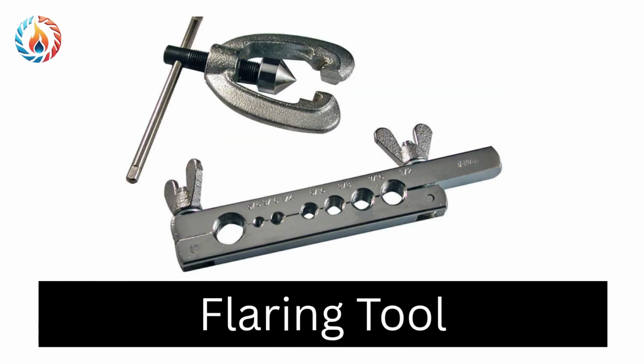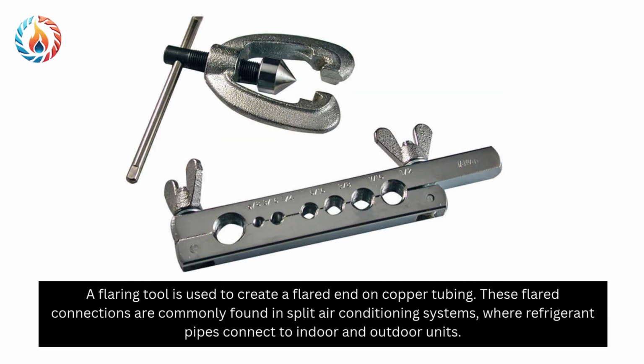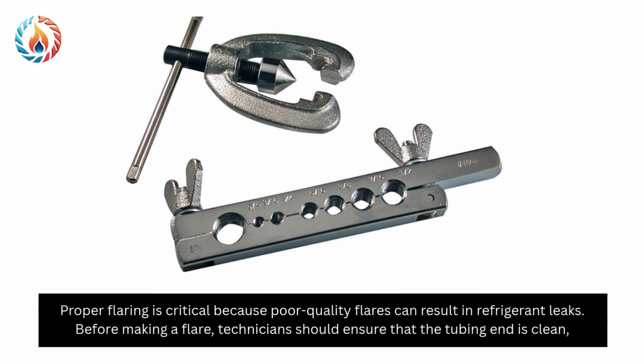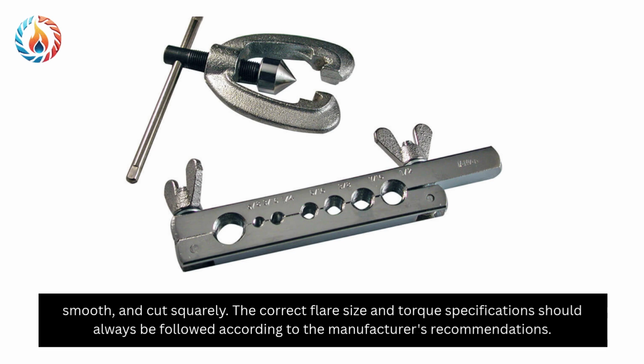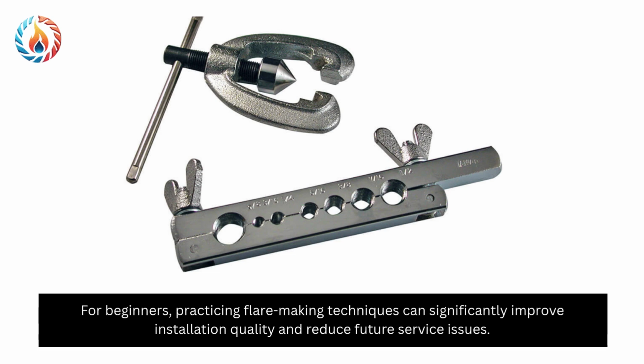Flaring tool. A flaring tool is used to create a flared end on copper tubing. These flared connections are commonly found in split air conditioning systems, where refrigerant pipes connect to indoor and outdoor units. Proper flaring is critical because poor quality flares can result in refrigerant leaks. Before making a flare, technicians should ensure that the tubing end is clean, smooth, and cut squarely. The correct flare size and torque specifications should always be followed according to the manufacturer's recommendations. For beginners, practicing flare-making techniques can significantly improve installation quality and reduce future service issues.